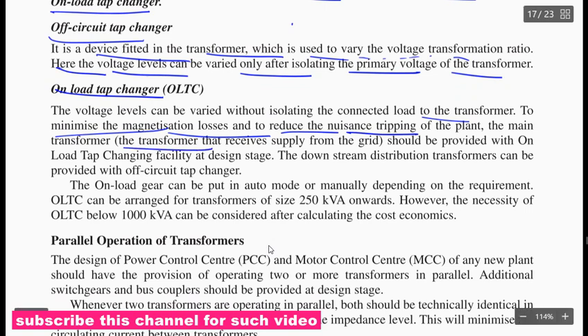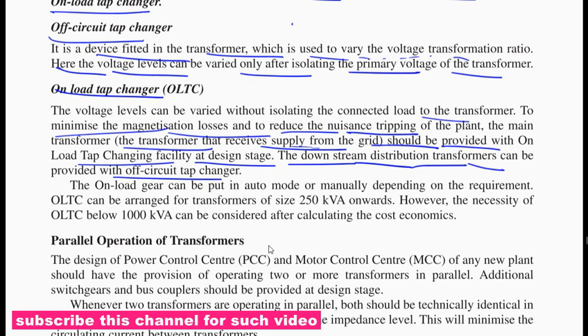The main transformer receives supply from the grid. Such transformers should be provided with tap changing facility at the design stage. The downstream distribution supply can be provided with an off circuit tap changer. On load gear can be put in auto mode or manual depending on the requirement. OLTC is arranged for transformer sizes of 250 kVA onward. However, the necessity of OLTC below 1000 kVA can also be considered by calculating the cost economics.